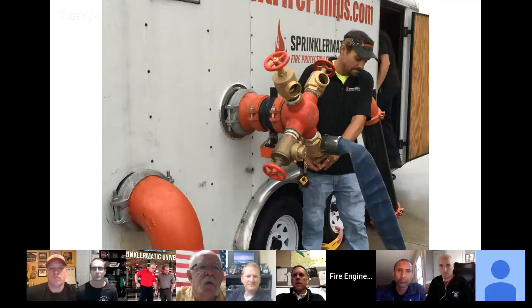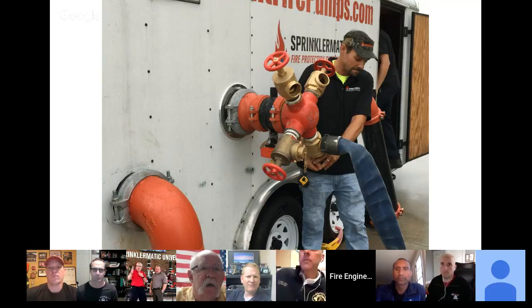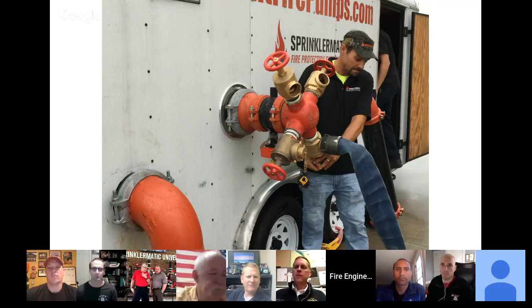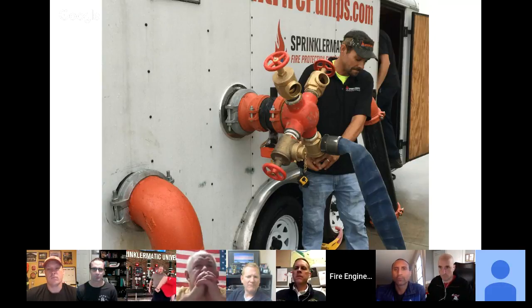That's Adam Kroll conducting a flow test out of the test header of this fire pump. You've got a test header, a fire department connection, a jockey pump controller for the electric jockey pump, and a controller for the diesel fire pump. It was just a wonderful experience. Let's see if you have any more pictures there, Sarah.